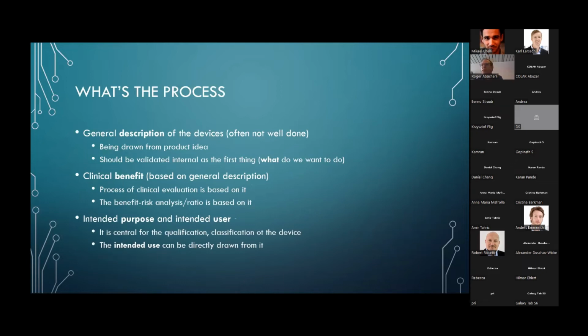So what is the process? And I'm showing just the results, not showing where this is coming from, with a small explanation on the next slide. So just to give me a chance to show what the results are before I explain why. So what you need first is a general description of the device, often not well done. That's an experience I have seen, being drawn from the product idea. That should be validated internally as the first thing, which claims what we want to do as a manufacturer. The second thing is that you describe the clinical benefit based on the general description, which is then used for the process of clinical evaluation and which is needed for the benefit-risk analysis ratio.